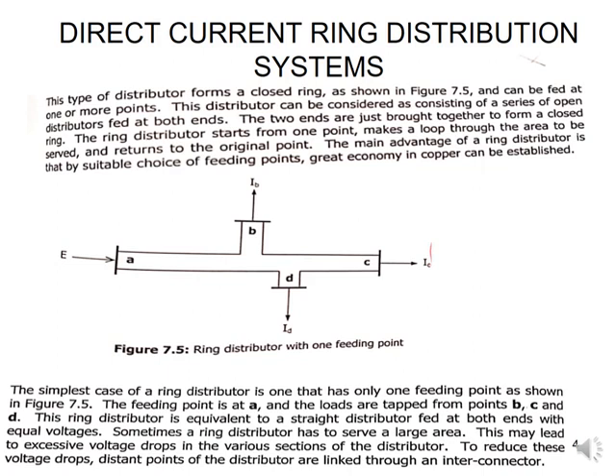The advantage is that by suitable choice of feeding points, you could have greater economy in the copper used in the system. Your line length might be shorter than going from A to D or A to C directly, because now you're just going from A to B and D to A, with shorter lines in between. The simplest case of a ring distributor is one with only one feeding point. Point A is the feeding point, and loads are tapped at B, C, and D, represented by IB, IC, and ID.